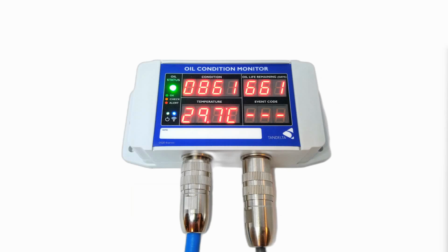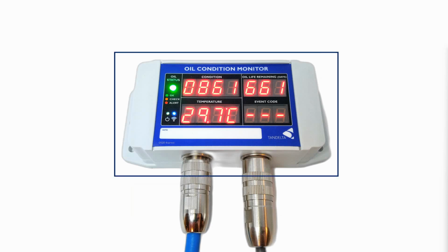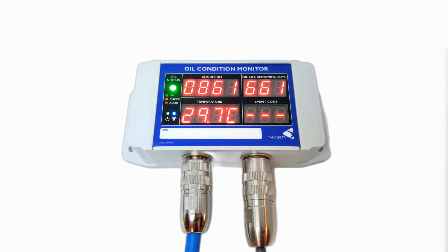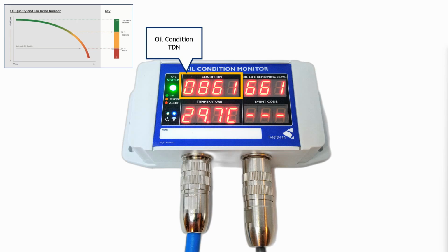Now we'll take a look at the data displayed on the TAN Delta Sense2 kit. The Sense2 is designed for a standalone installation on any equipment. It's rugged and has an easy to read display, even in direct sunlight. In the top left-hand corner of the display, you can see the TDN displayed. This value shows you the overall condition of the oil for your equipment. The TDN limits change based on your application, and these limits can be found on our website and in our documentation.